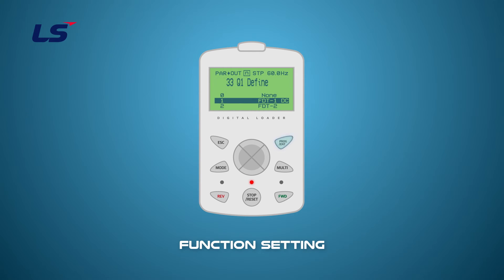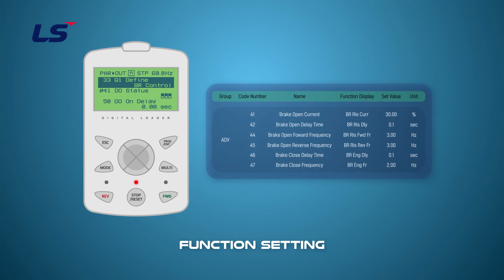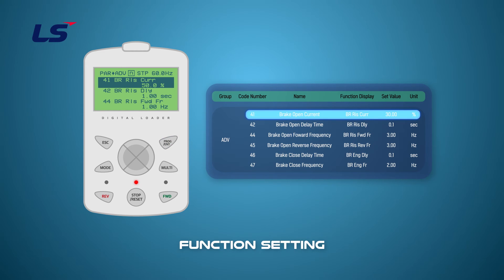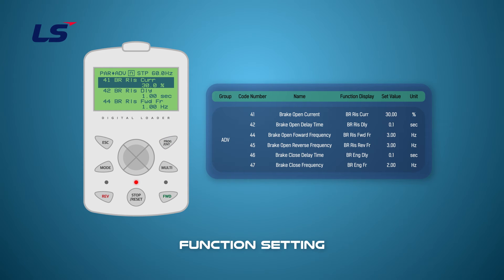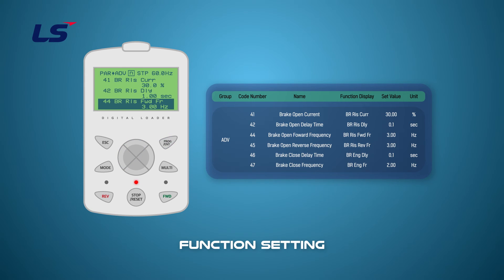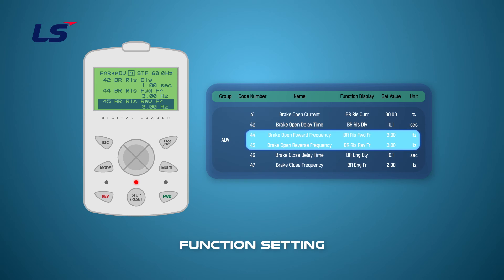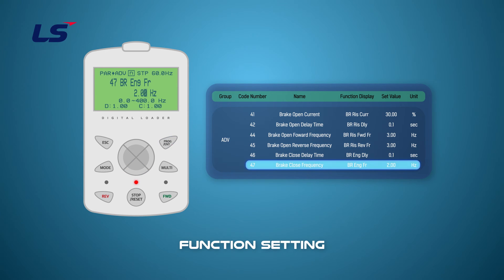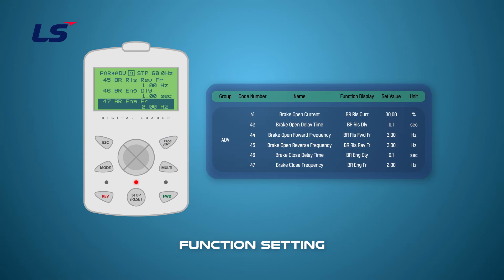Set 35 BR control for the output at outgroup 33 Q1 define. The BR control function sets the open-close frequency and the open current. ADV41 brake open current is the value based on the rated current of the motor. Similar to setting outgroup 57 FDT frequency, set the brake open frequency at ADV44 and ADV45, and set the close frequency of the brake at ADV47 in deceleration of motor.